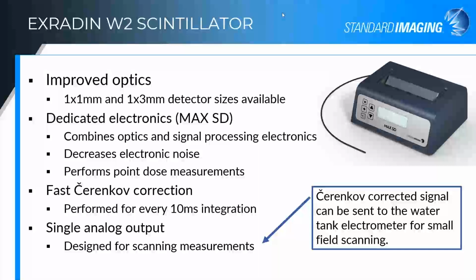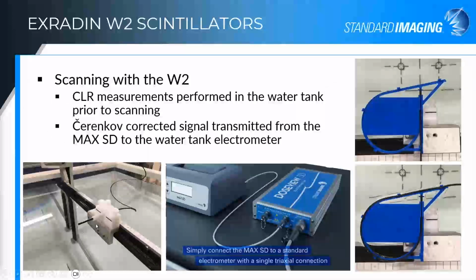The other advantage of the W2 and its electrometer is called the Max SD for scintillation dosimetry. The Max SD can do that Cherenkov correction every 10 millisecond integration, and then convert that digital signal back into a corresponding analog output that is linked to your Cherenkov corrected measurement, and output that as a current that can be read in by your 3D or 1D water tank scanning system. So the Max SD then becomes, actually I think I have pictures on the next slide, this pass-through where you would put your scintillation detector.